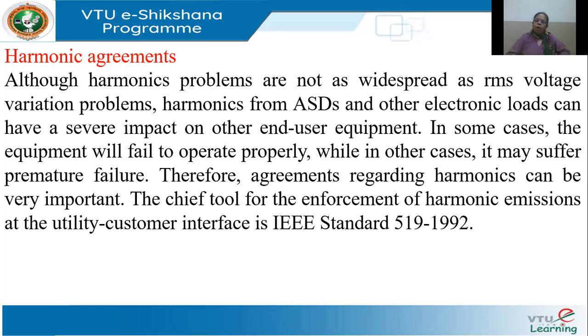So, very early on, we have seen that harmonics is a problem mostly created by the loads, the kind of loads we have: non-linear loads, computing loads, automatic speed drives, lighting loads, SMPS, chargers, so many different kinds of loads. These are all sources of harmonics. Okay, so these may permanently damage the equipment, or equipment may maloperate. And the IEEE 519-1992 standard tells you what harmonic levels are to be maintained.